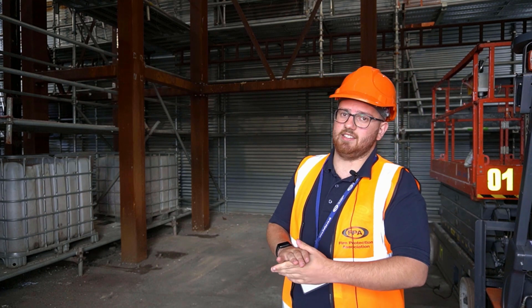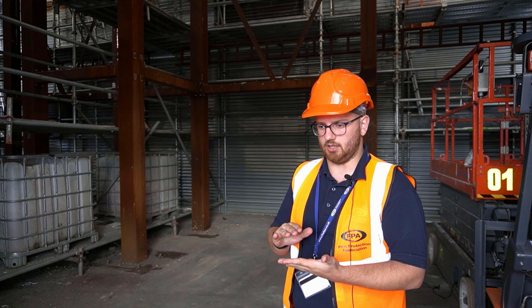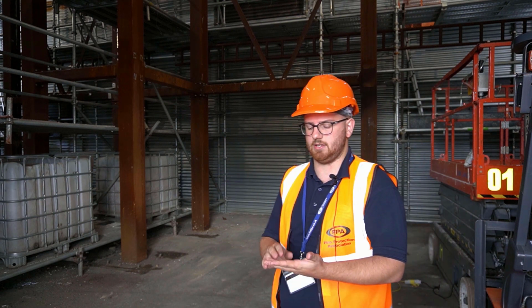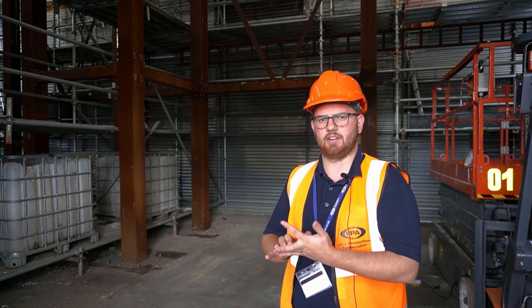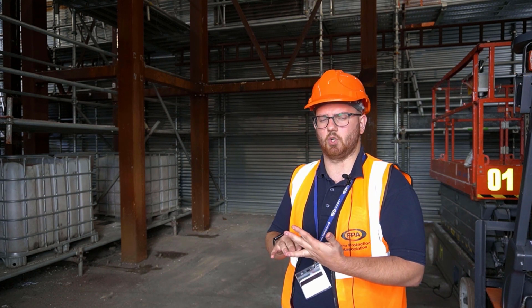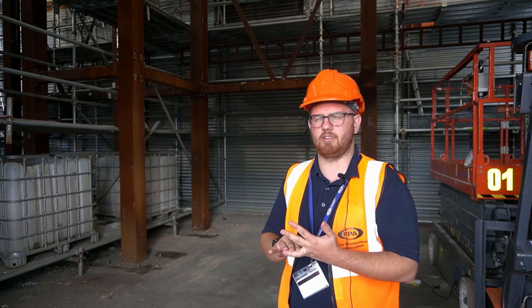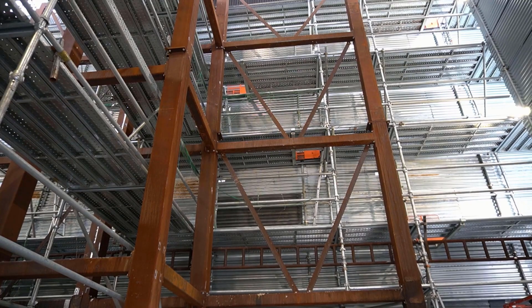But the actual test itself, generally, in terms of the time spent assembling the wall, we generally say it takes between 2 and 3 weeks to actually build a cladding system for the test, and then any curing time that is required will be added on to the end of that, and then we will test it the final week, and it can only be demolished 2 or 3 days after the test has happened. So we're generally talking from a minimum of around 3 weeks for a test to a maximum of really around 7 to 8 weeks for most systems.